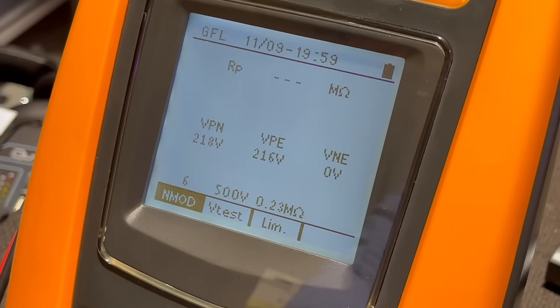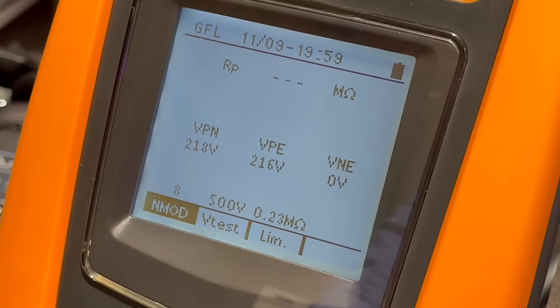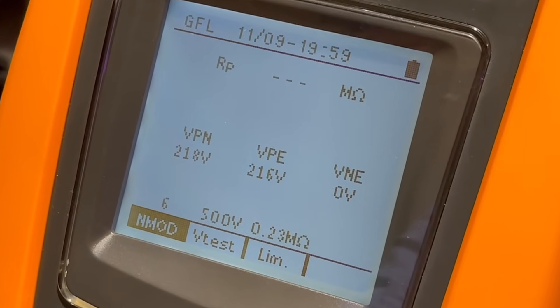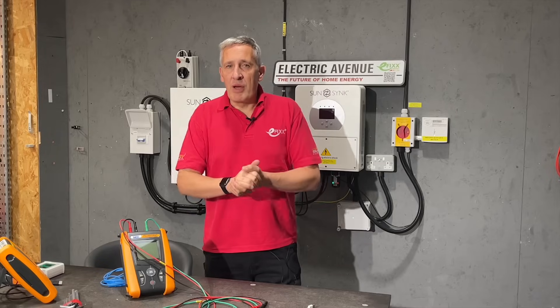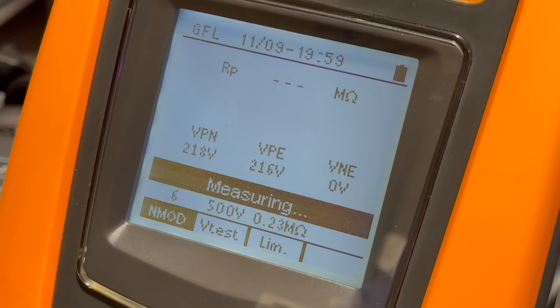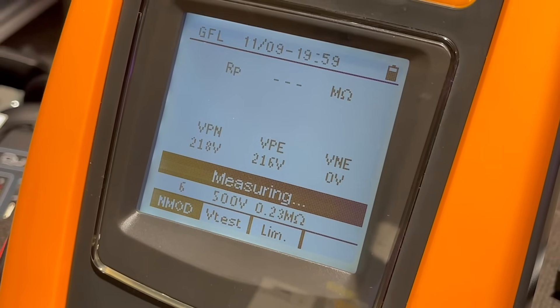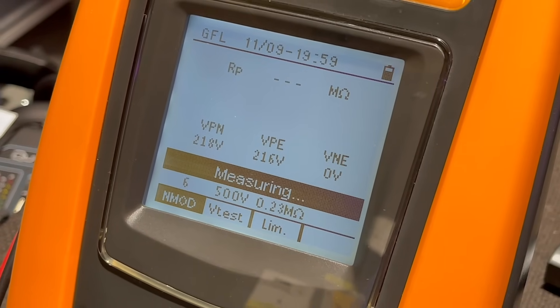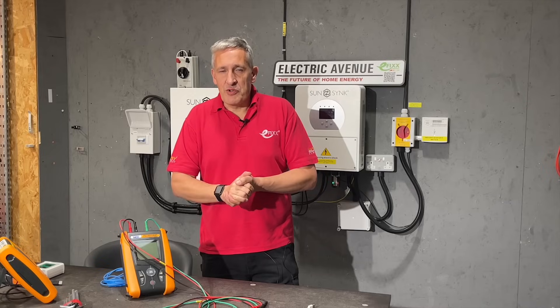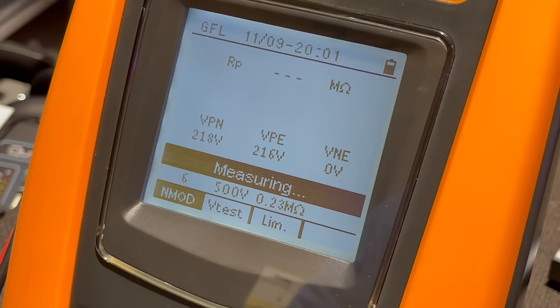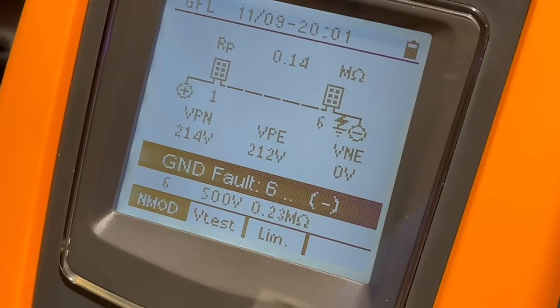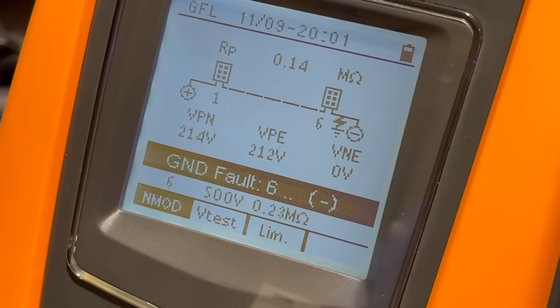On this screen we can again set the test limit, but we also have to specify the number of solar modules in the string, up to a maximum of 35. So again we'll set the test running, but this time the result should tell us exactly where the fault is within our solar module string. And we can see on the screen that we have a fault in the negative connection leading out to module 6.